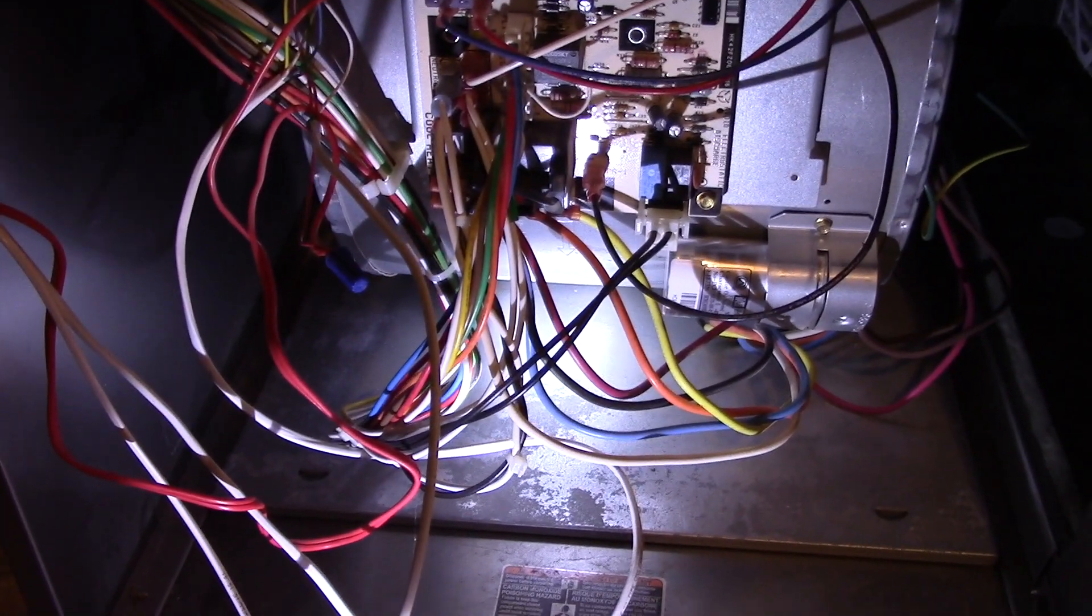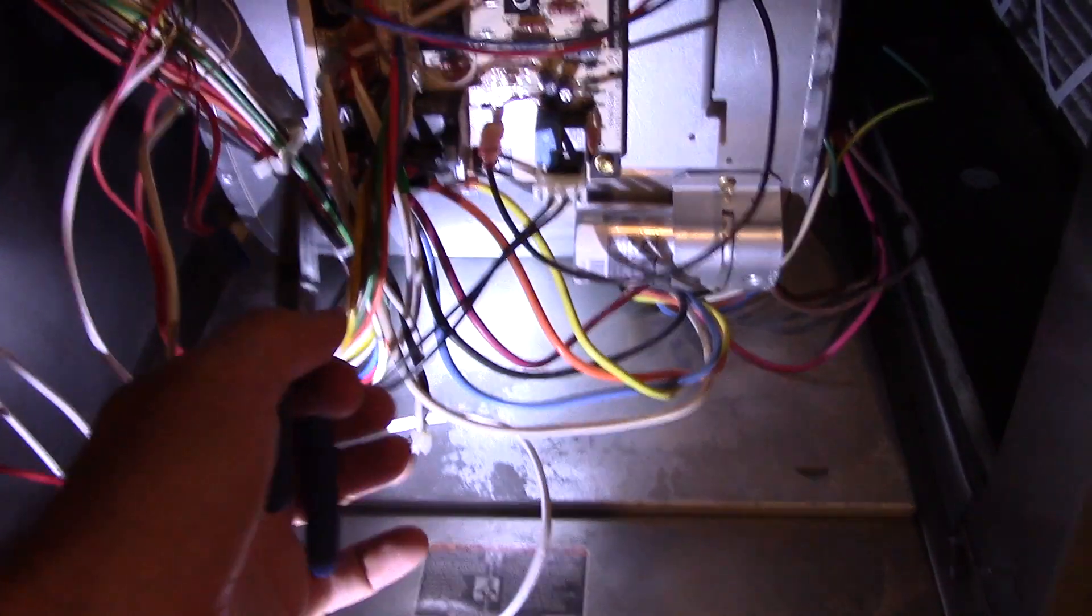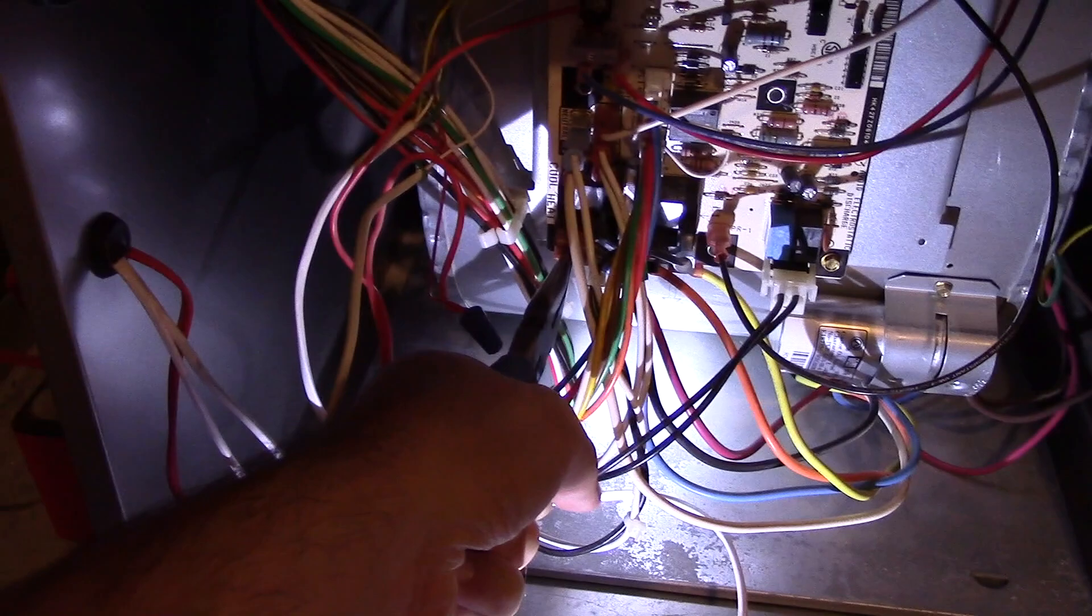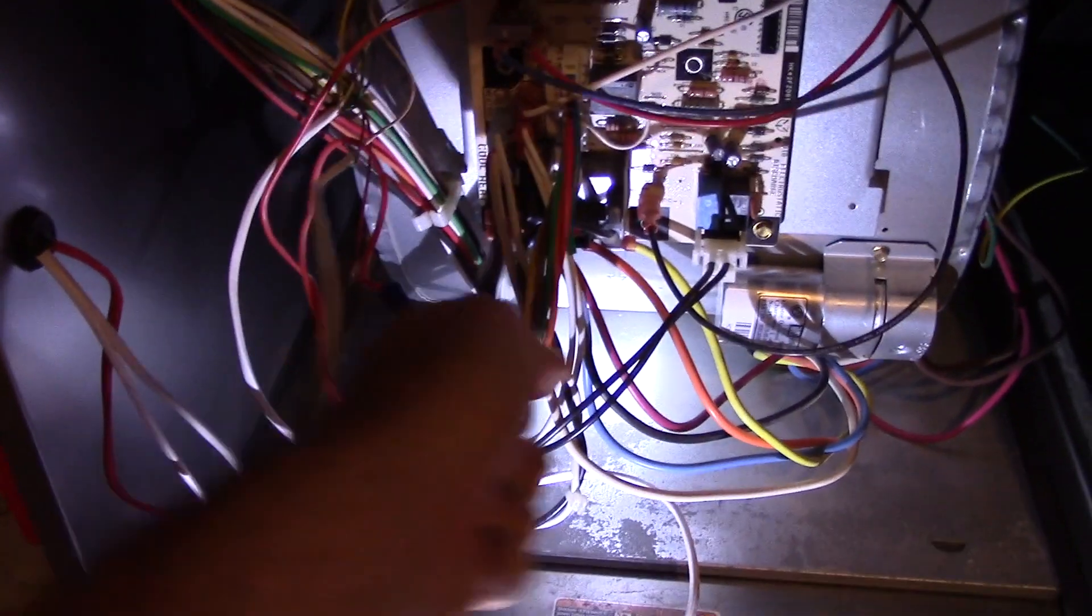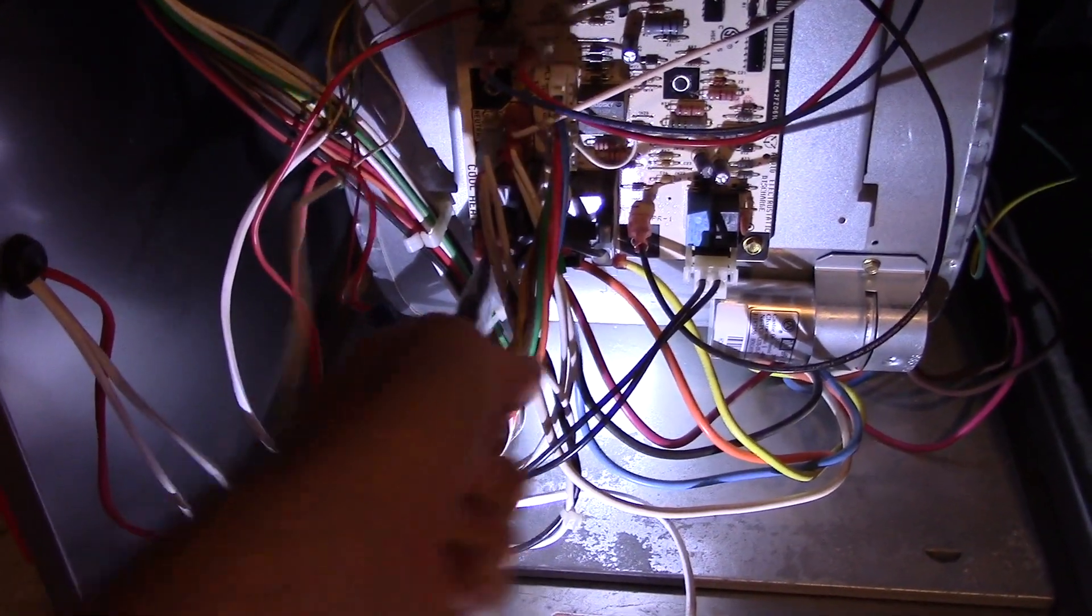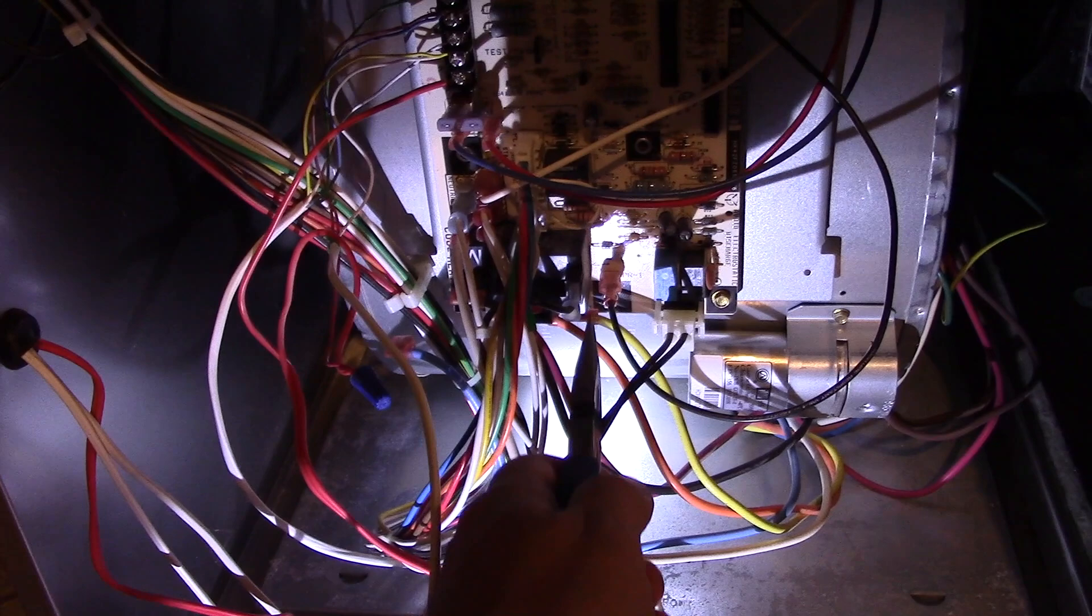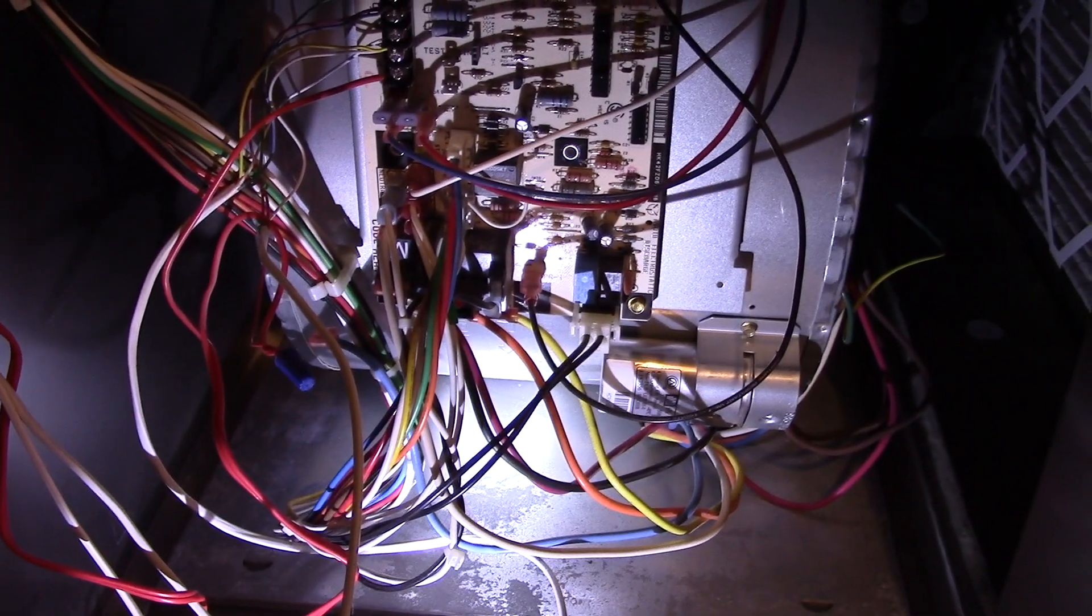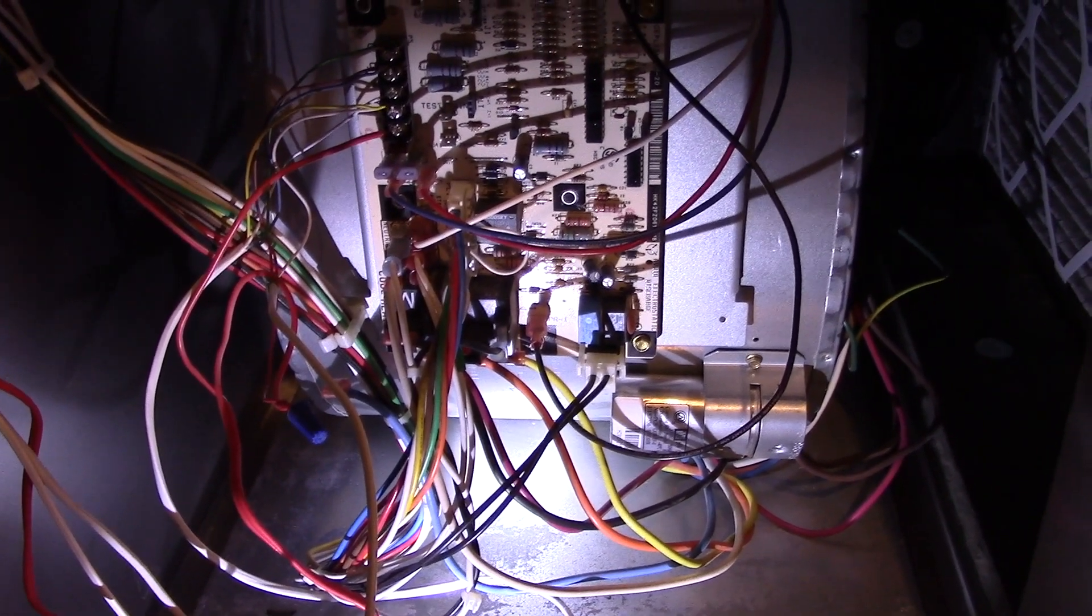What you would basically do is, with needle-nose pliers, and again, be absolutely sure the power is off on the circuit board, you just grab one of the wire connectors. Grab onto it firmly, not too tight, but firmly, and when you try to pull it off, wiggle back and forth, because you don't want to just try to pull straight off because you don't want to damage the board. Just give it a little bit of force. See? Came off not too bad. Then you would simply pull the yellow wire off the spare terminal in the exact same way, and just move it onto the terminal for the heating speed.